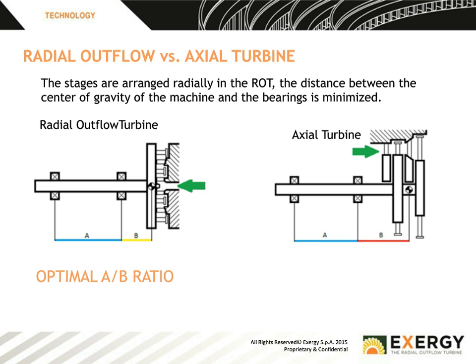Also good to notice here that the blade height of the axial turbine increases as it goes from the inlet to the outlet. So that's as the fluid moves from the inlet to the outlet. That blade height is the only way that the fluid gets to expand. You have to have a small blade at the beginning and a large blade at the end. And you're very limited on what is practically possible in terms of blade height.